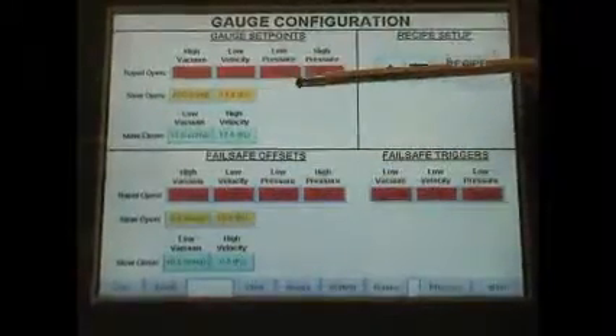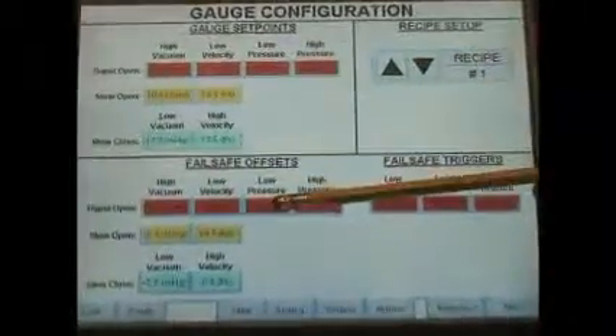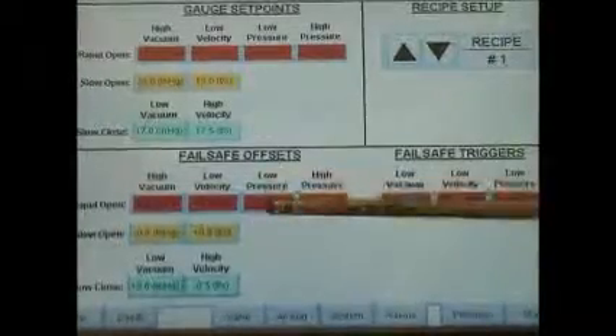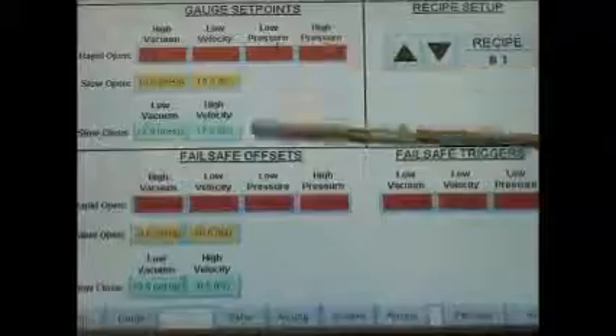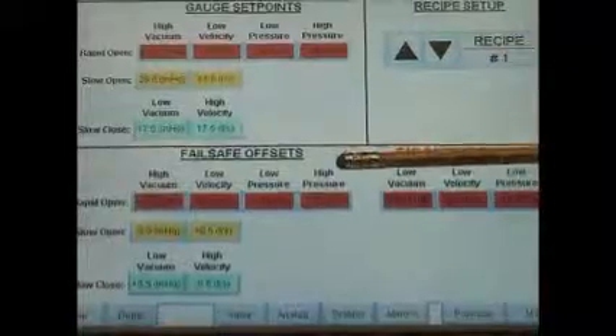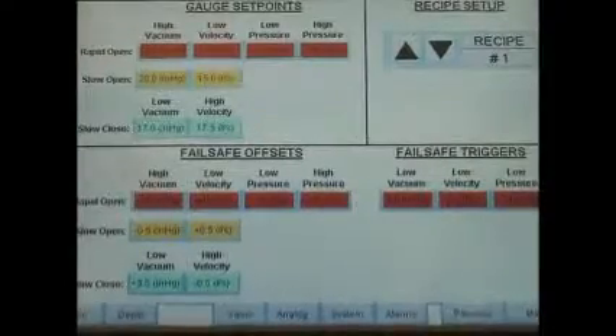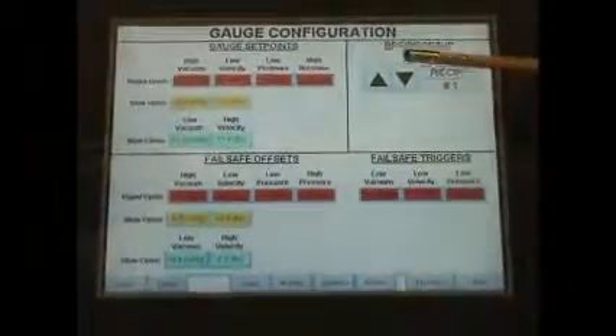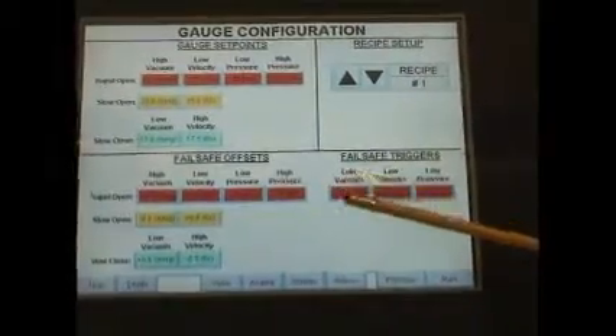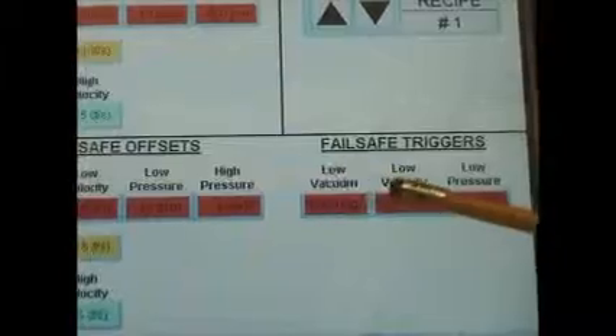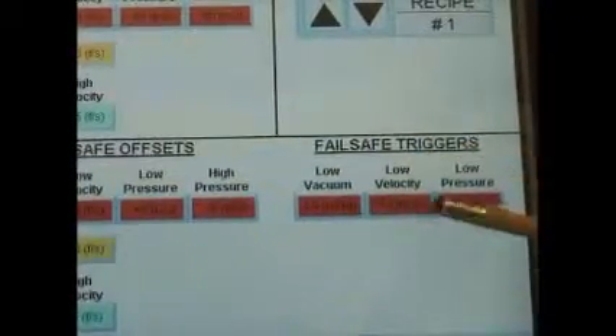Just keep in mind that, for example, let's look at pressure. Our low pressure now is set at 40. If we fall into a fail-safe mode, our pressure is now going to trigger opening at 45 because we have a +5 here. So that means we're going to add 5 to this. Same way in our high pressure. We're at 80 and we are going to then reduce our high pressure by 5, narrowing up our green band in the event of a fail-safe mode happening. The fail-safe triggers can be triggered by vacuum transducer failure, a velocity meter failure, or a pressure transducer failure.